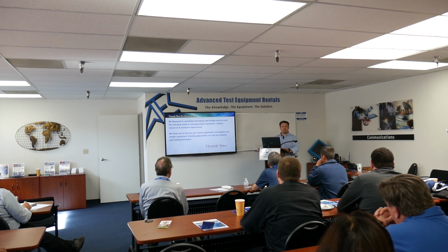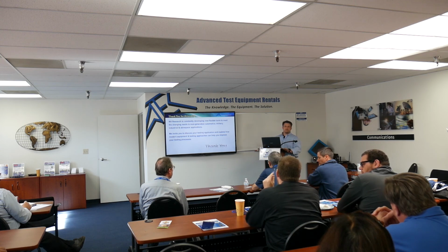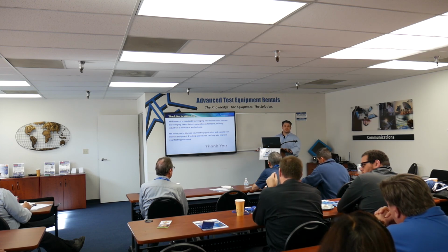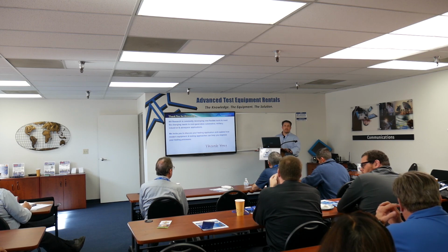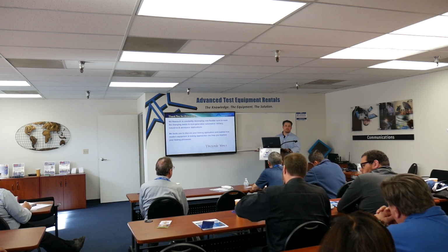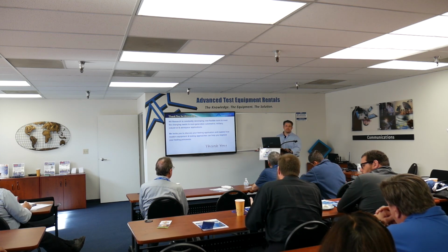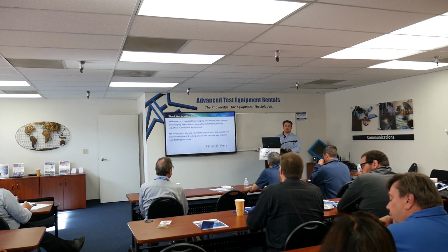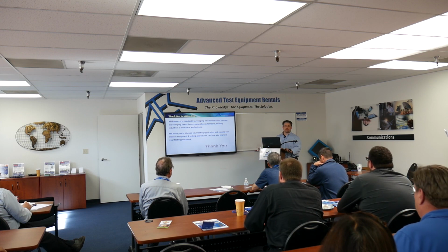Other customers make that digital output, and the harmonics it creates interfere with the electronics we want to test, so we don't get the right results. With an analog output, we know we're feeding 50, 60 hertz in. That's what you will see on the mains test. Yes, you see all the junk in the normal mains too, but not for test purposes. Yeah, that's the question.